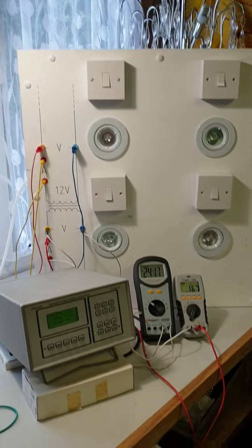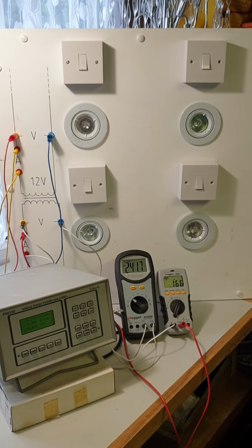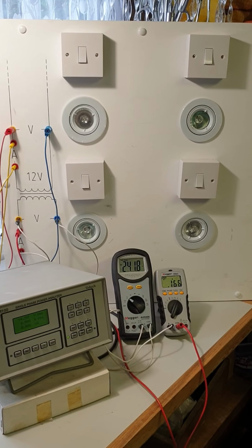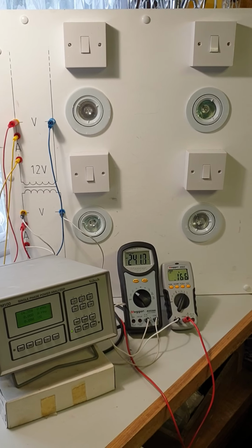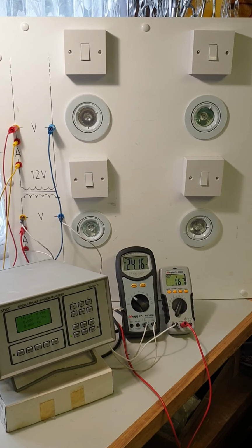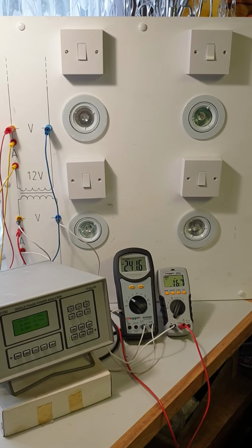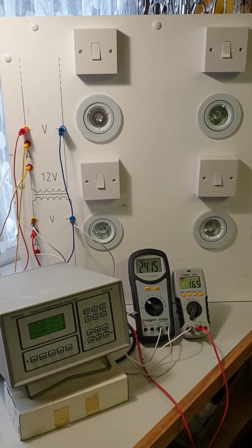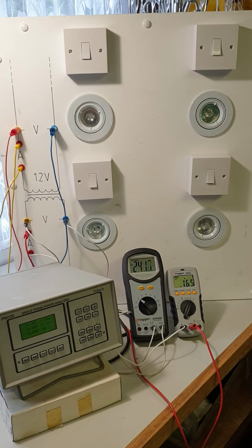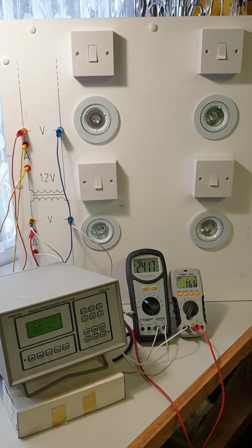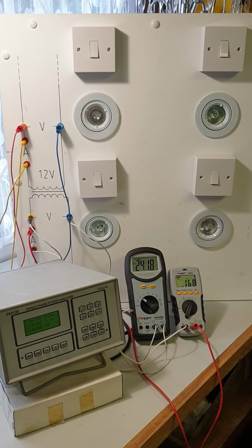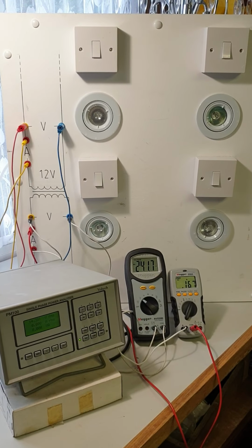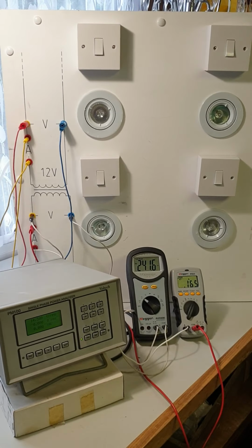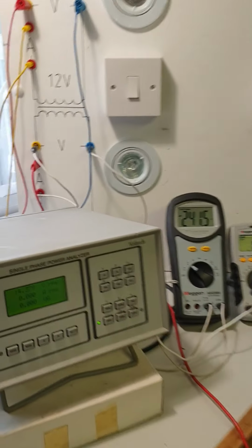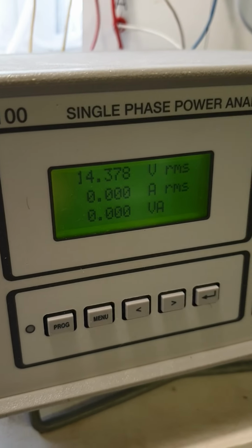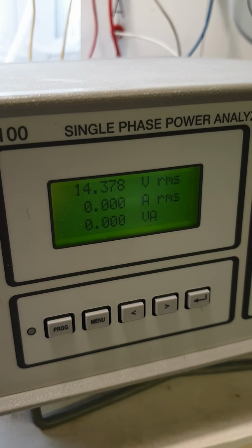Okay, a transformer under full load, the voltage drops because you're pulling more current. Just like loading someone up with bags of cement. They're not as tall as they were when they had no bags. The more bags you put on, the more they go down. Transformer is exactly the same. So with full load, the voltage drops. With no load, the voltage will be at its maximum value of 14.378 volts RMS here.